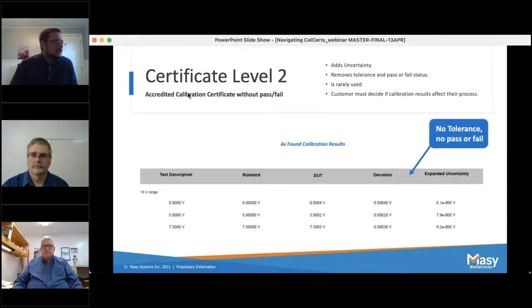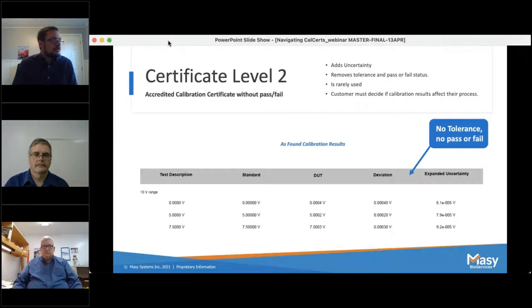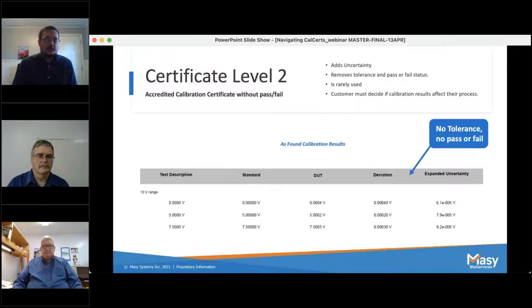This is an example of a level two certificate. The biggest thing with this is there's no tolerance and no pass or fail. This does add measurement uncertainty. It's a certificate that's not always used a lot. If you request a certificate like this, you need to look at the deviation and see if it affects your process. Mike is now going to shed some light on why a level two certificate may benefit an FDA-regulated business.